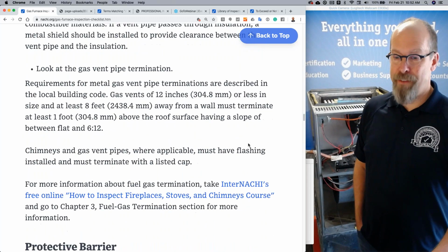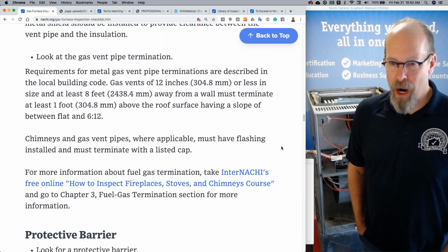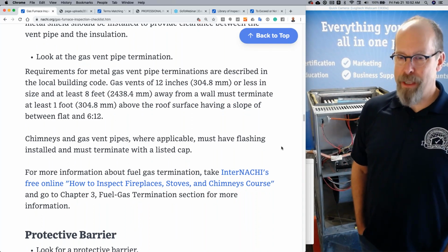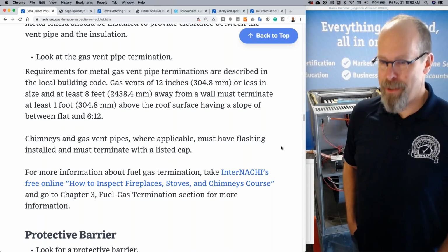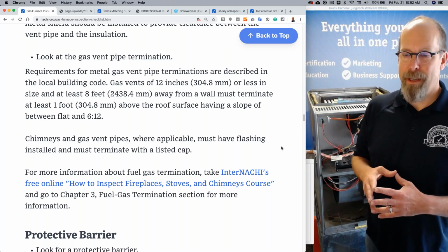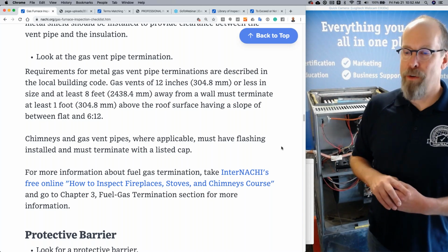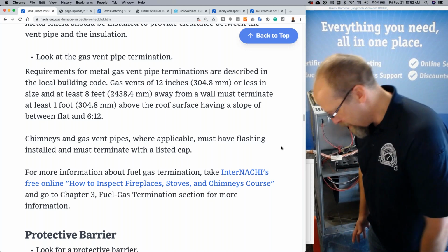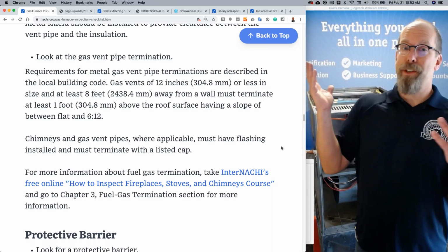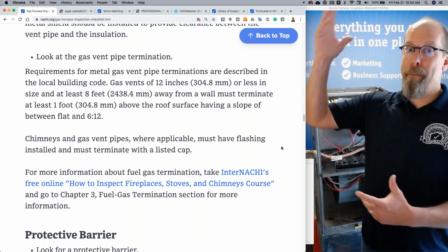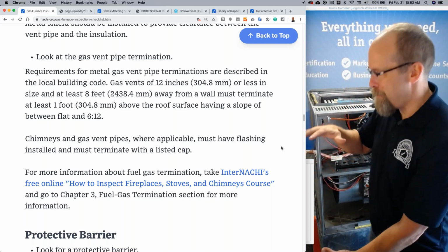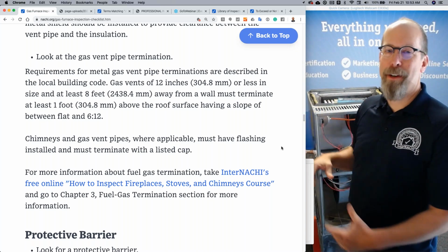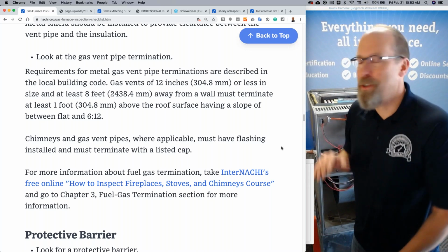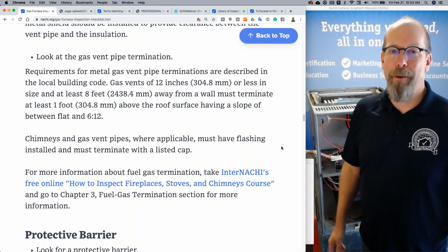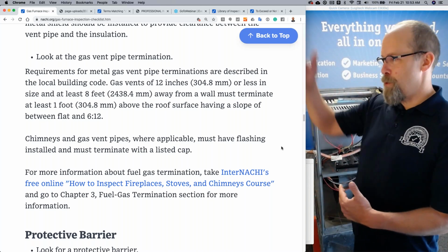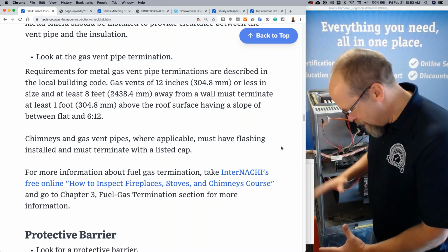So look at the gas vent pipe termination. This could be confusing for a lot of inspectors. Requirements for metal gas vent pipe terminations are described in the local building code. And gas vents 12 inches or less in size and 8 feet away from a wall must terminate at least a foot above the roof surface. So when you are walking on a roof and you have a gas-fired heating system and it's category 1, mid-efficiency, let's say like this fella, with a metal vent pipe, and you're looking at the height of the chimney stack, let's call it, of that gas appliance and the termination of it, and it looks really short, only about a foot, maybe a foot and a half, it's probably okay. It's common, unless it's a high slope roof or some other exceptions and provisions, it's probably right.